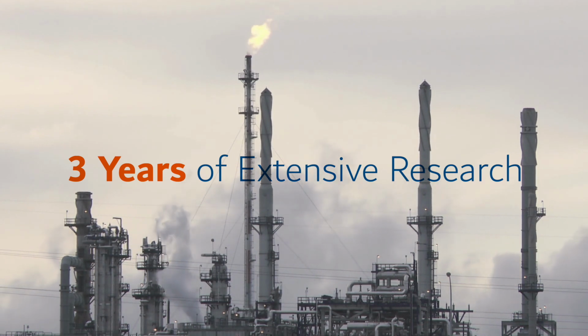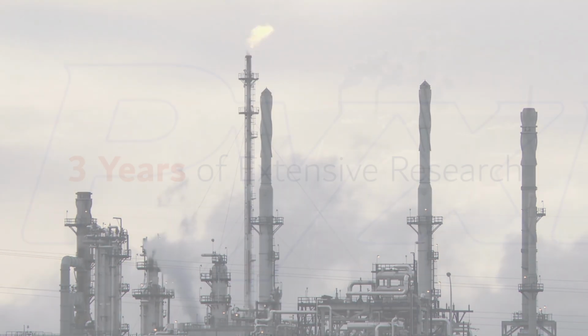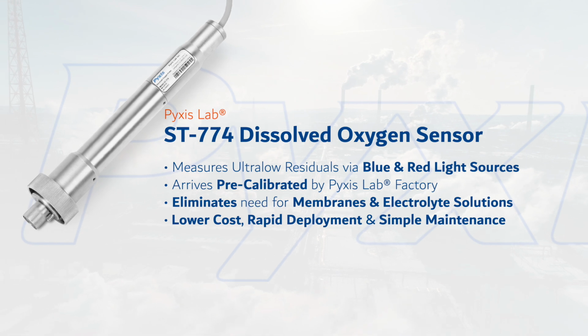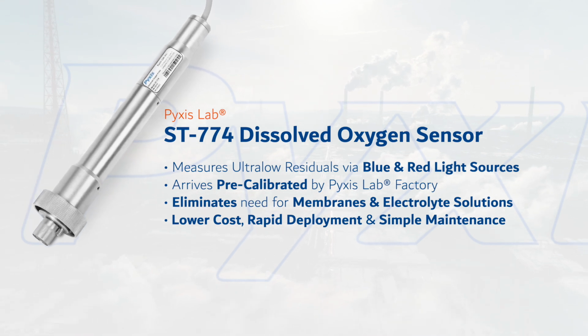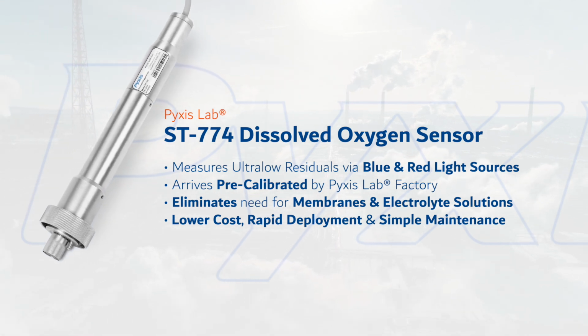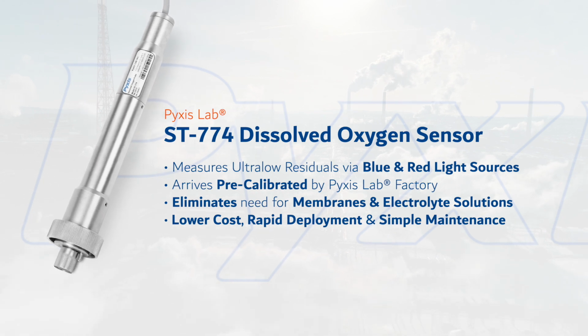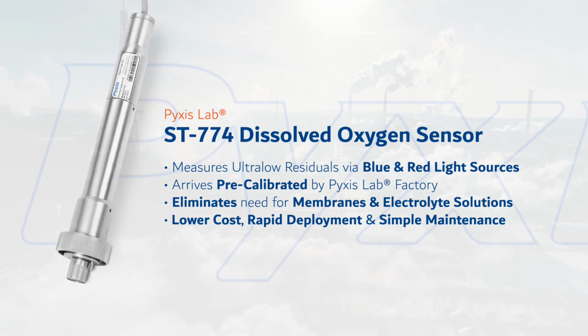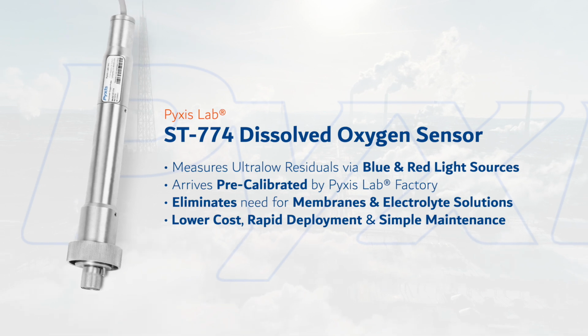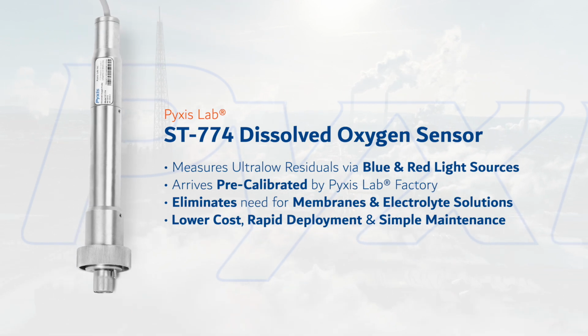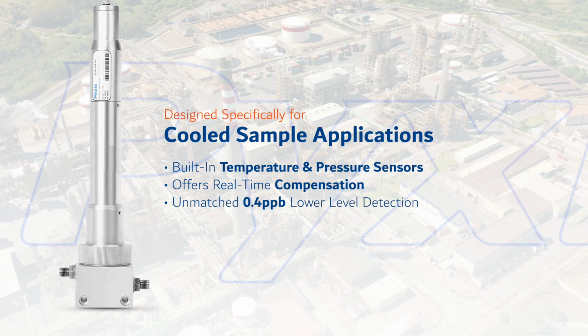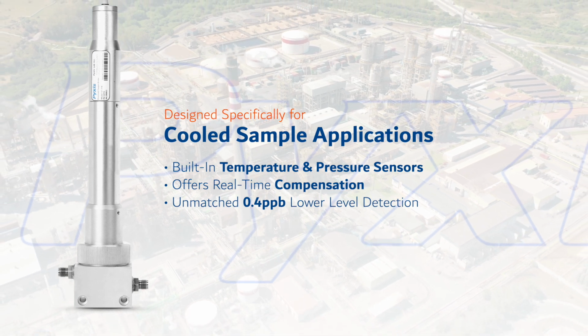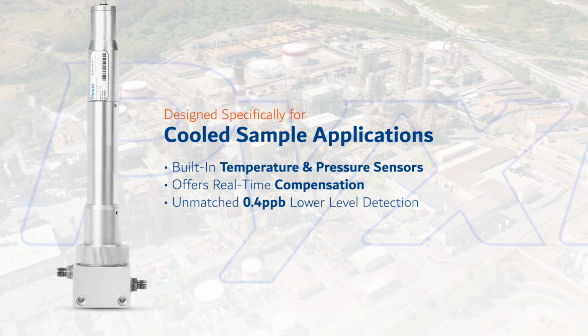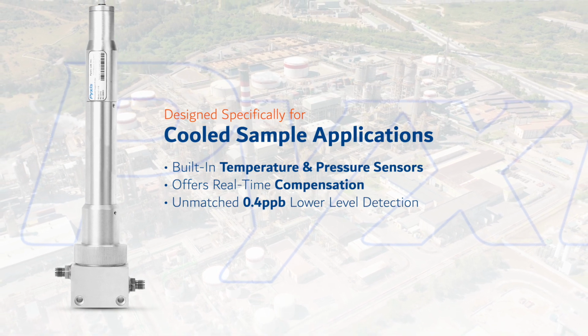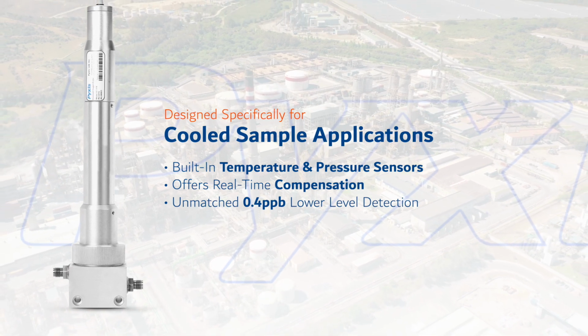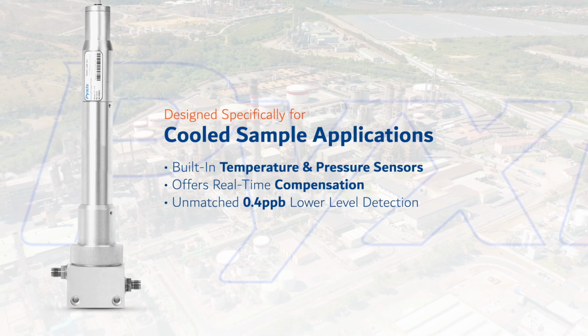It incorporates a fully optical platform measuring ultra-low residuals of dissolved oxygen via blue and red light sources. The ST-774 is a fully integrated state-of-the-art smart sensor that comes calibrated from Pyxis factory, enabling rapid deployment and simple maintenance and calibration for years of service. The unique design completely eliminates the need for membranes and electrolyte solutions. Designed specifically for cooled sample applications measuring ultra-low concentrations of dissolved oxygen, the ST-774 includes integrated temperature and pressure sensors providing real-time compensation based on sample conditions of the installation.